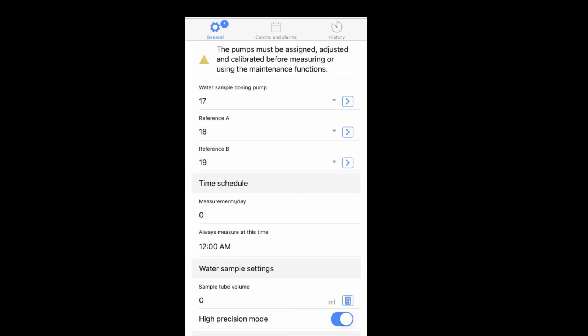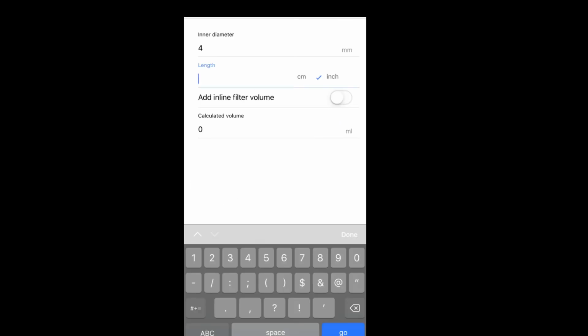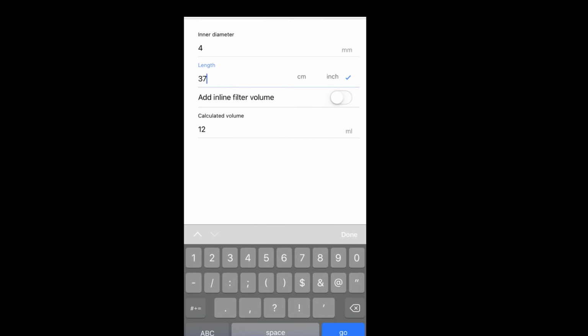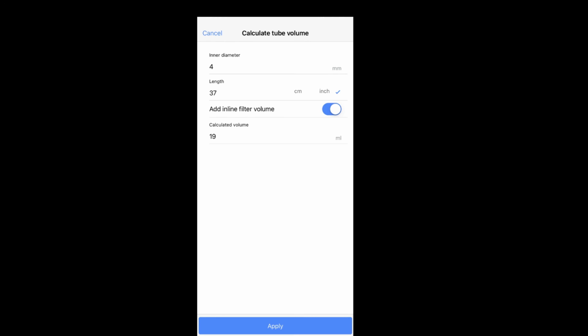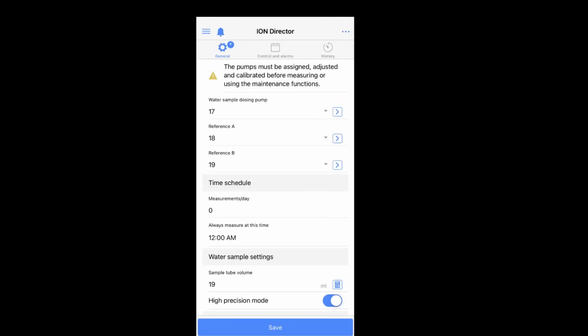Next, we need to enter the sample tube volume. Scroll down to the water sample setting and click on the calculator on the right-hand side. A new menu will appear asking you to enter the length of your dosing tube to help you calculate the volume. In my tank, my dosing tube length to the inlet side of the water filter was 32 inches, and from the water output side to the doser was 5 inches. Therefore, I would enter 37 inches. Then I would click on the Add Inline Filter button, and then the calculated volume would appear. Then click Apply, and this will apply the water sample volume to the water sample settings.